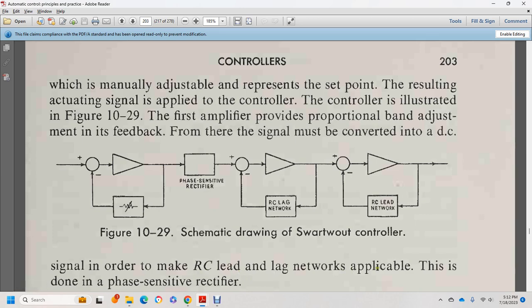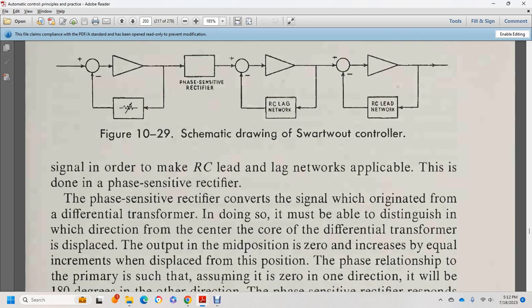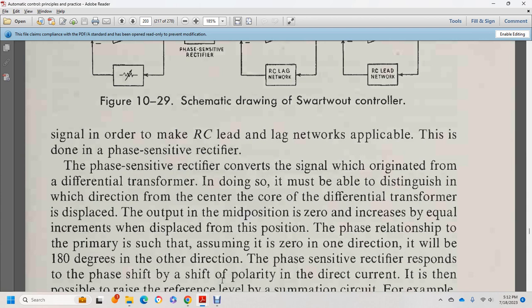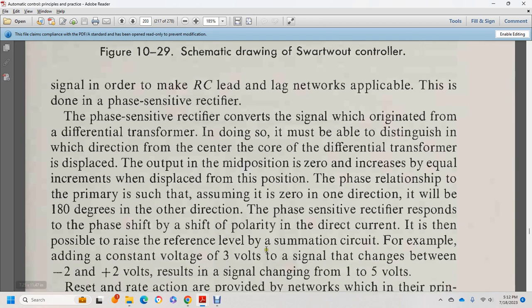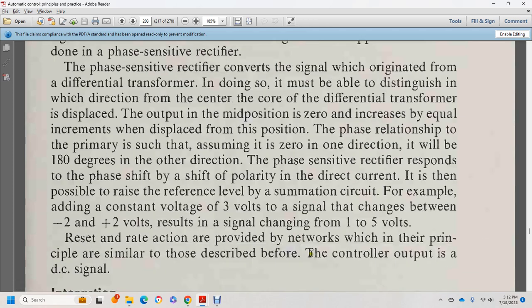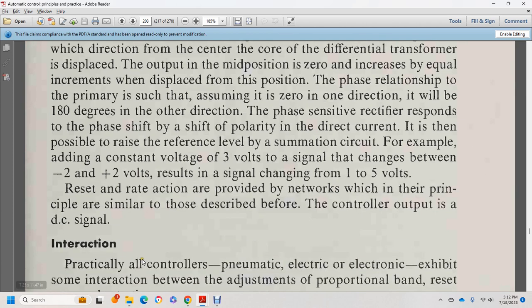To make the RC lead-lag network applicable, the AC signal is processed by a phase-sensitive rectifier. The signal originates from the differential transformer. The direction of displacement of the differential transformer coil from mid-position: displacement in one direction produces one phase; displacement in the other direction produces a phase 180 degrees opposite. The rectifier problem of phase shift is resolved by adding a constant voltage level — for example, adding a constant 3 volts to a signal changing between −2 and +2 volts results in a signal changing between 1 and 5 volts. Reset rate and rate action are provided by networks similar to those previously described. The control output is a DC signal.